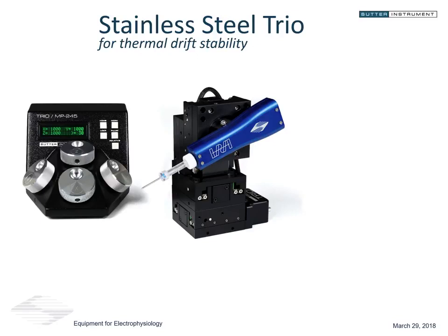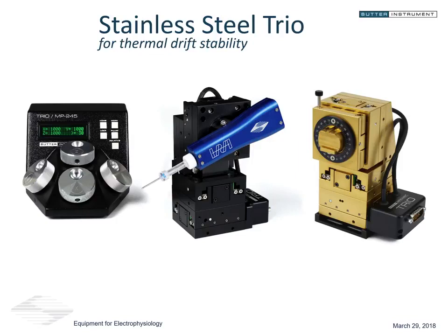So as the temperature in the room changes slightly, the aluminum can either expand or contract slightly, which then moves our pipette tip, which can be detrimental to our experiment. If instead we utilize a different material, we can actually reduce that thermal drift considerably. So in this case, we actually have a stainless steel version of our Trio, the Trio designed for high stability, which adds even more stability to the manipulator itself.